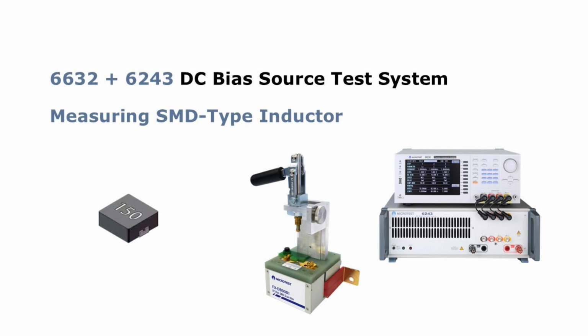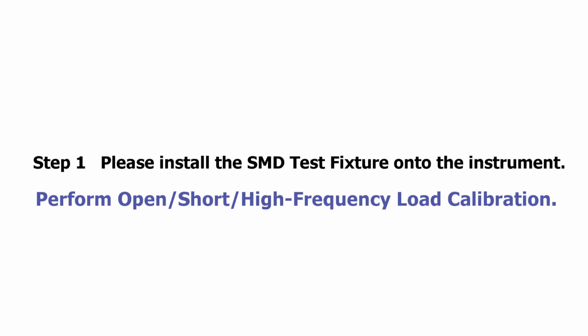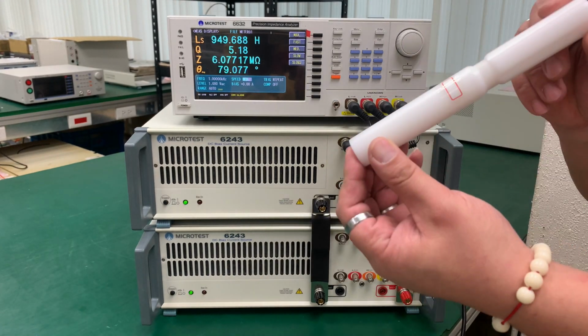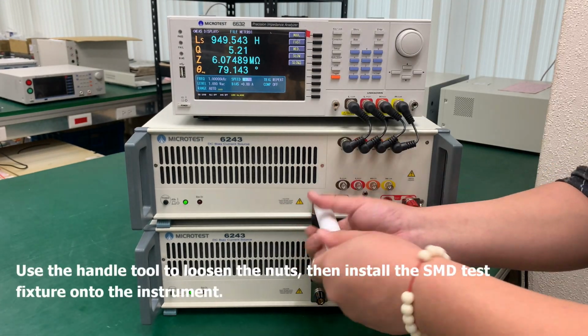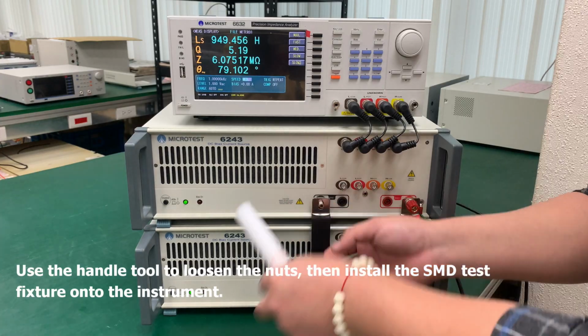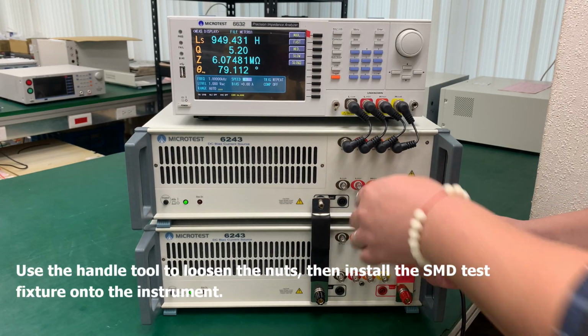Join me in measuring SMD-type inductors and analyzing their magnetic saturation current and temperature rise current characteristics. Step 1. Please install the SMD test fixture onto the instrument. Use the handle tool to loosen the nuts, then install the SMD test fixture onto the instrument.